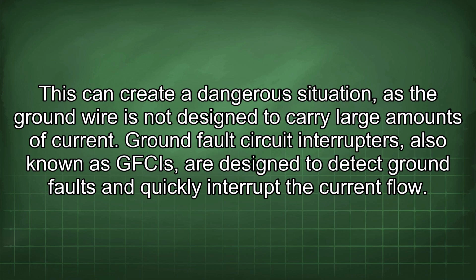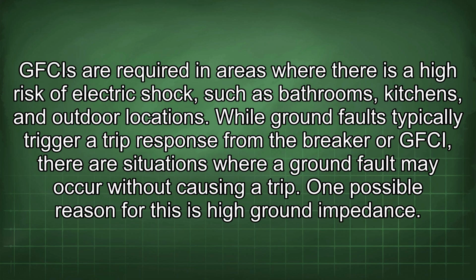This can create a dangerous situation, as the ground wire is not designed to carry large amounts of current. Ground fault circuit interrupters, also known as GFCIs, are designed to detect ground faults and quickly interrupt the current flow. GFCIs are required in areas where there is a high risk of electric shock, such as bathrooms, kitchens, and outdoor locations. While ground faults typically trigger a trip response from the breaker or GFCI, there are situations where a ground fault may occur without causing a trip. One possible reason for this is high ground impedance.